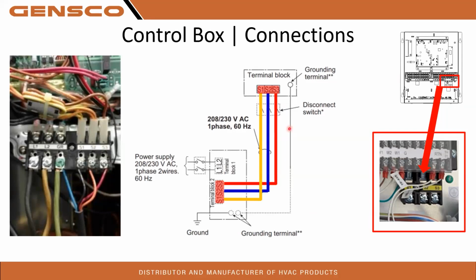Typical S1, S2, S3. Disconnect switch, make sure to use a 3-pole disconnect when required. So Mitsubishi does not require these on the system. That is up to local codes. If your local code requires a disconnect, then you will want to use a 3-pole disconnect. If you use a 2-pole, then you can still have high voltage on that S3. Dangerous situation. Don't want to put anybody's lives at risk. So make sure to use a 3-pole disconnect on that.